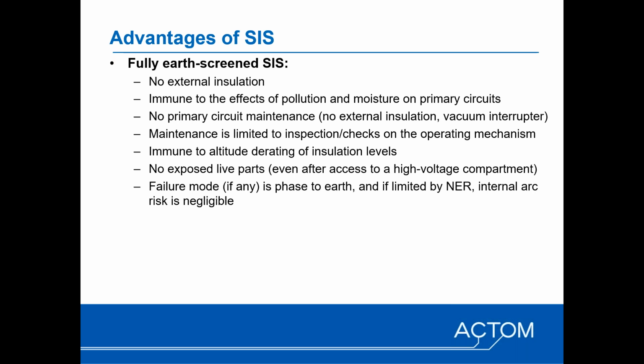There are no exposed live parts, even after accessing a high voltage compartment, due to the earth screen layer on the surface of the switchgear. The failure mode, if any, would be phase to earth, particularly where each individual phase is individually screened and earthed. And if, as in the case of South Africa, the fault levels are limited by an NER, a neutral earthing resistor, the risk of internal arc is effectively negligible.